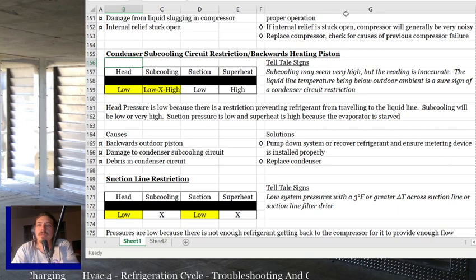And if that's restricted, or you've got a metering device on the outdoor unit as it exits the subcooling circuit, then you can have a restriction there, and it'll cause a problem. What you're going to see is low head pressure, and you'll have low to, doesn't make any sense, to super high subcooling. It all depends on what you have. The only time I've actually seen the issue with the backwards heat piston, the subcooling was like 60 degrees or 50 degrees or something ridiculous.